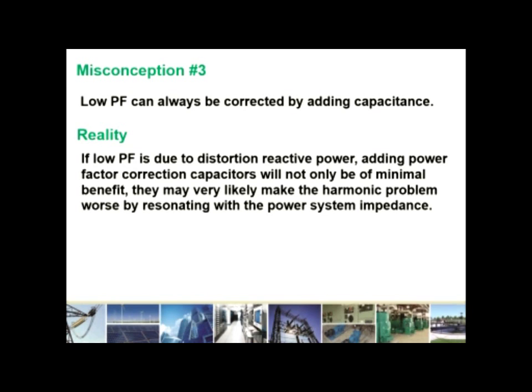So misconception number 3 is that low power factor can always be corrected by adding capacitance. In reality, if low power factor is due to distortion reactive power, adding power factor correction capacitors will not only be of minimal benefit, they may very likely make the harmonic problem worse by resonating with the power system impedance.